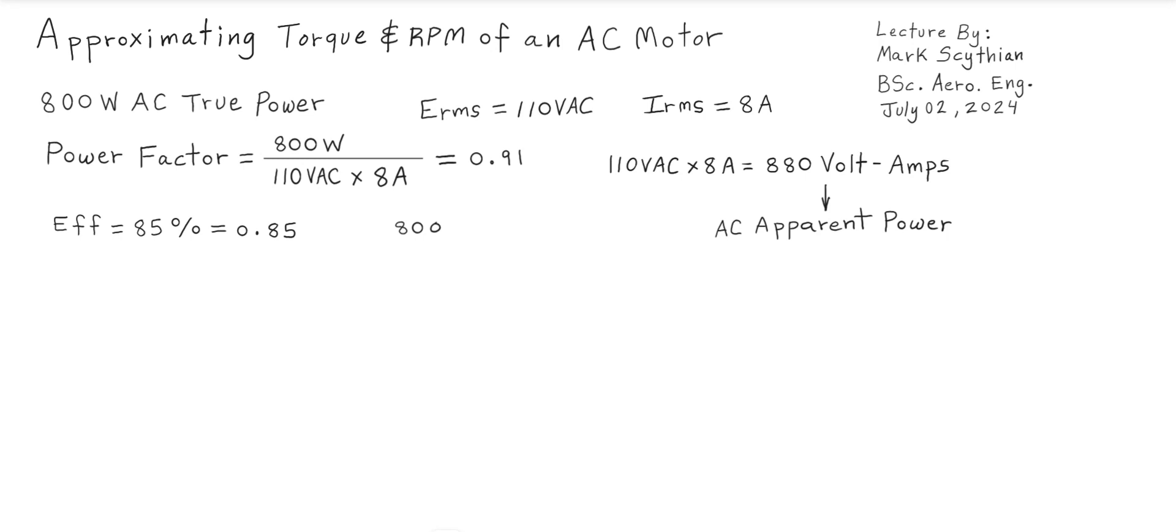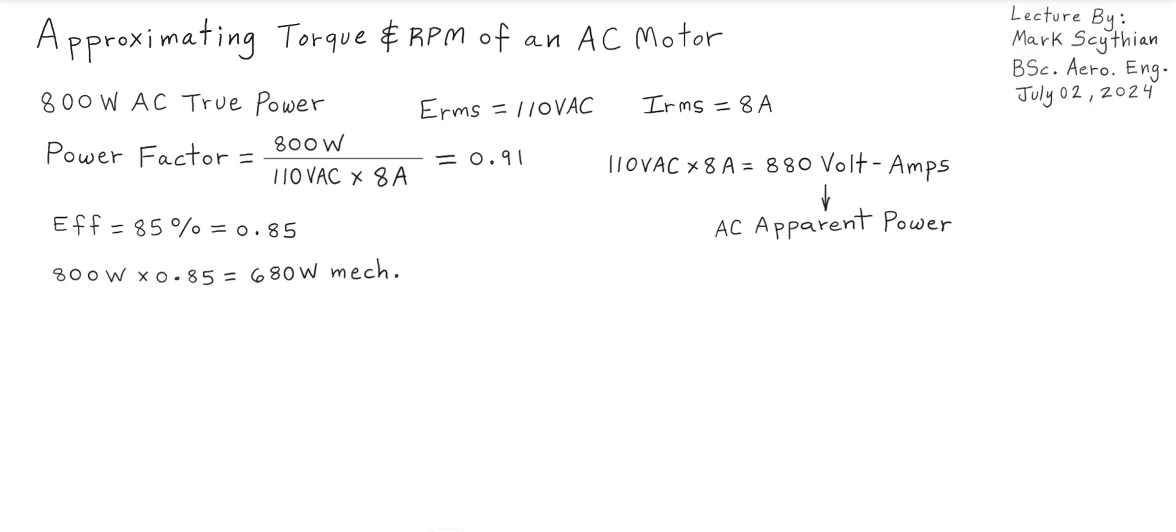So we have an AC electric motor with a power factor of 0.91, and assuming the electric motor has a typical AC electric motor efficiency of 85%, this will give us 680 watts of mechanical power output at the AC electric motor's output drive.